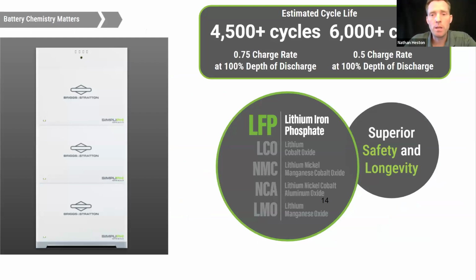We're sticking with LFP technology, and we've been able to increase the power output of these batteries. The individual modules themselves are capable of a 1C output, which means a single 6.6 kilowatt hour module can output 6.6 kilowatts of power, and that's a significant increase. A typical battery might be C/2 or C/3, meaning it can only safely be discharged in 2 hours or 3 hours. With a 1C charge or 1C discharge rate, these battery modules are rated at a very fast rate.